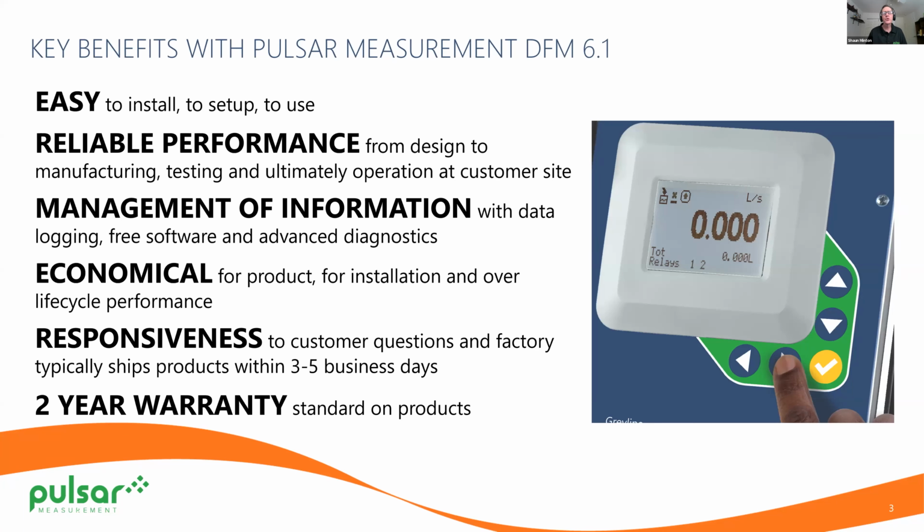With the Doppler Flow Meter, once you get the hang of it, you can set this up on any full pipe with suspended solids in about 5 minutes. It's really that simple. There's only a few key settings that you need to know, and then just let the device work its magic. That's the really great thing about it.